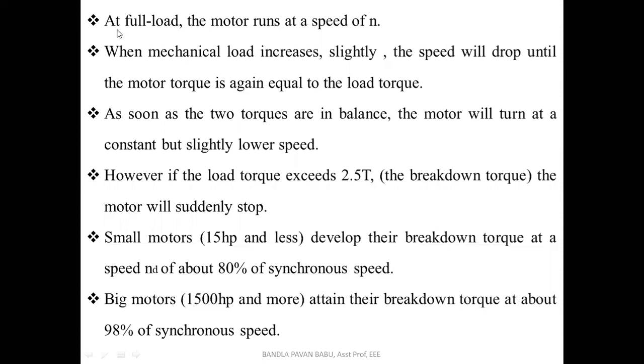Okay, so from this graph we have noticed all these points. At full load, the motor runs at speed of n, or capital N, that's up to you. When the mechanical load increases slightly, the speed will drop until the motor torque is again equal to the load torque. So if we keep on increasing the load, what happens? The speed gets reduced, and what about the torque position? It tries to reach the maximum torque.